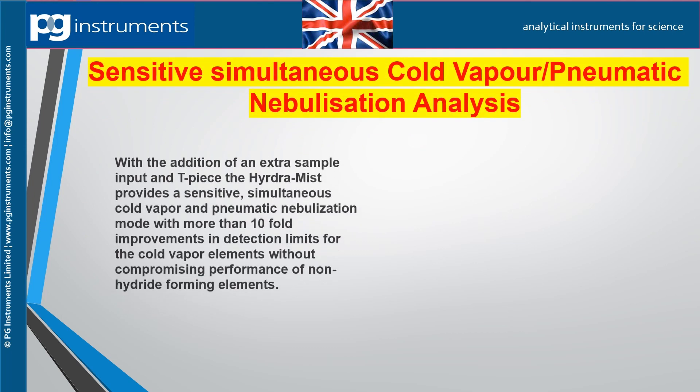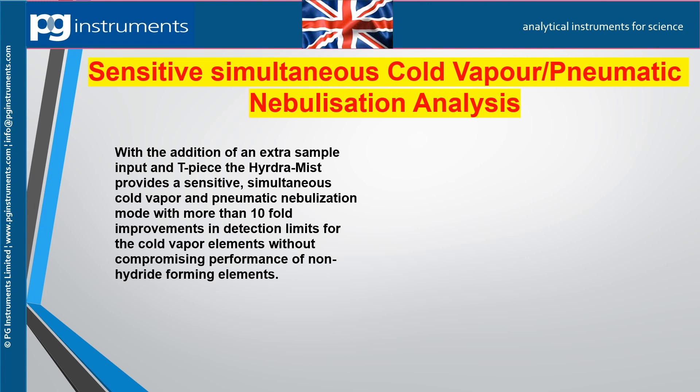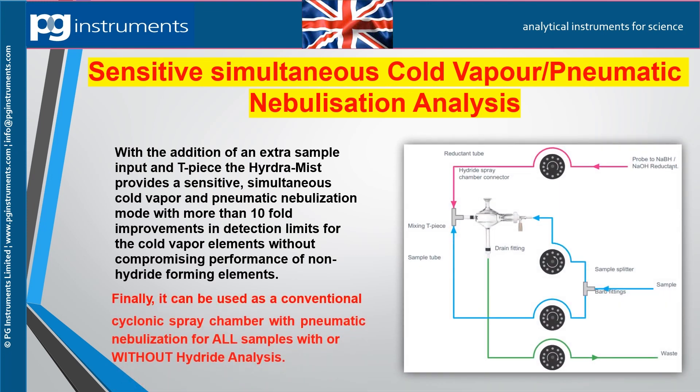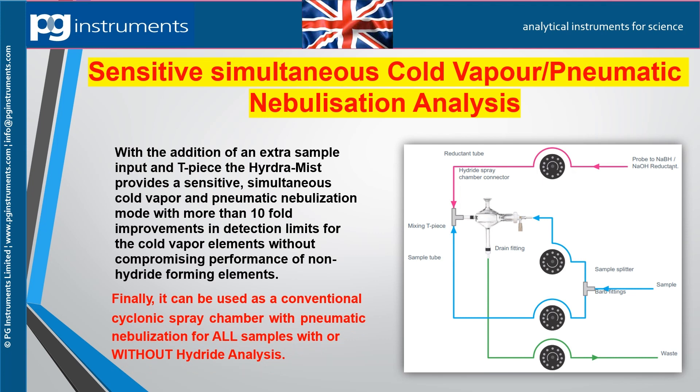With the addition of an extra sample input and T-piece, the Hydra-Mist provides sensitive simultaneous cold vapor and pneumatic nebulization mode with more than tenfold improvements in detection limits for cold vapor elements, without compromising performance of non-hydride forming elements. A four-channel peristaltic pump is required: one channel for reductant, two channels for the sample as it is split in two directions, and a fourth channel for the drain.